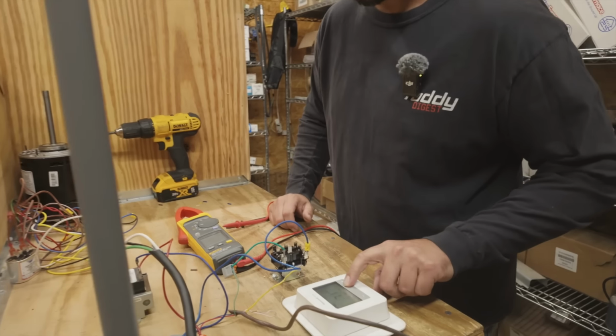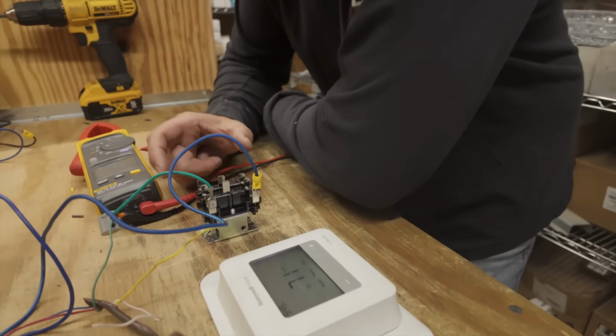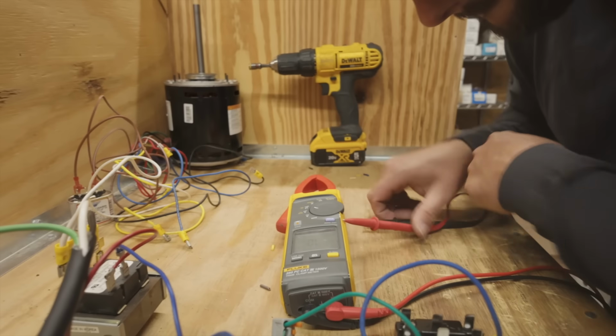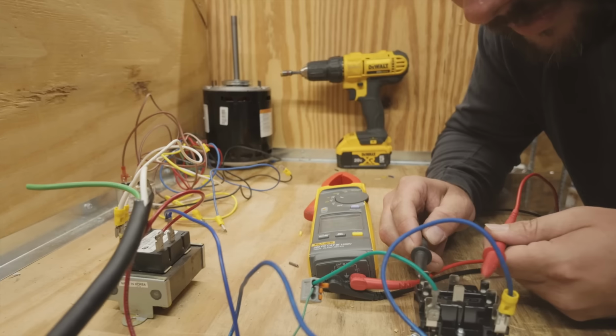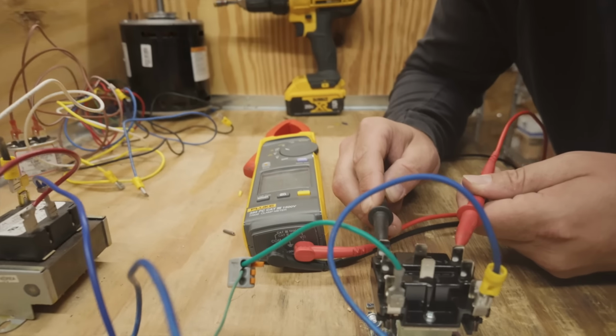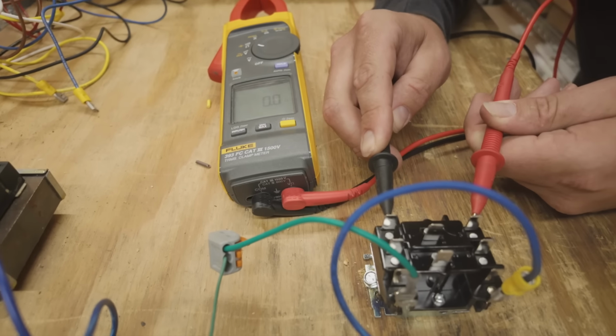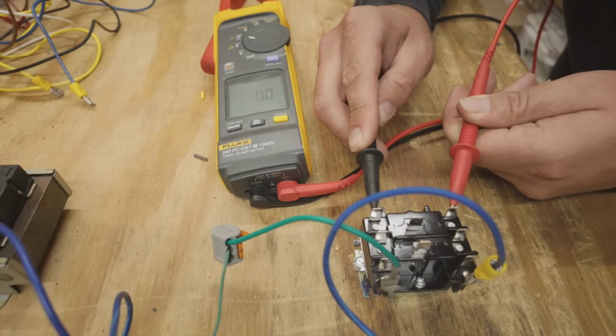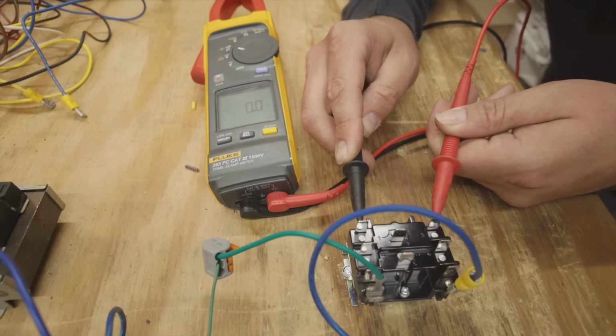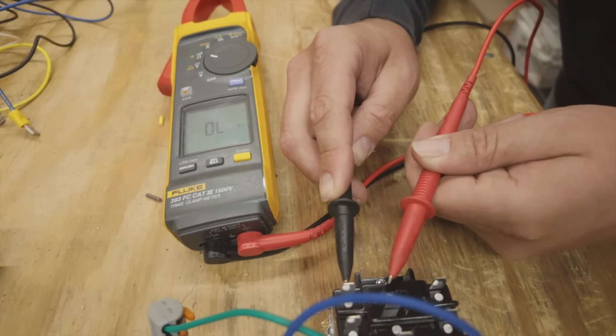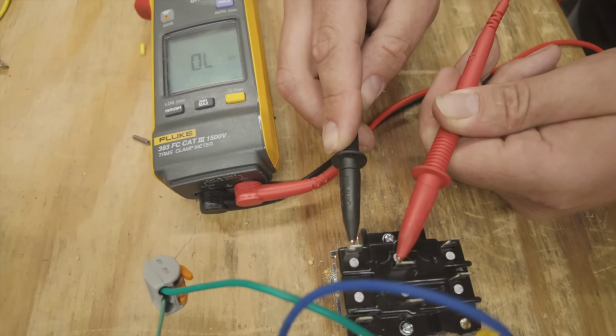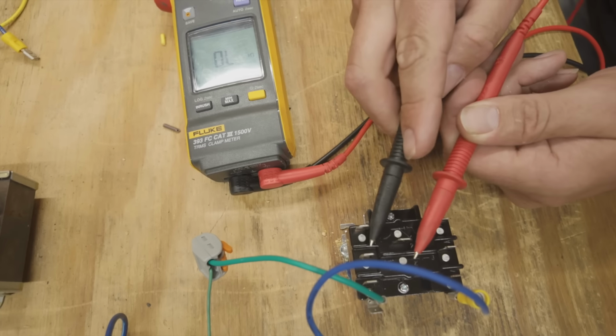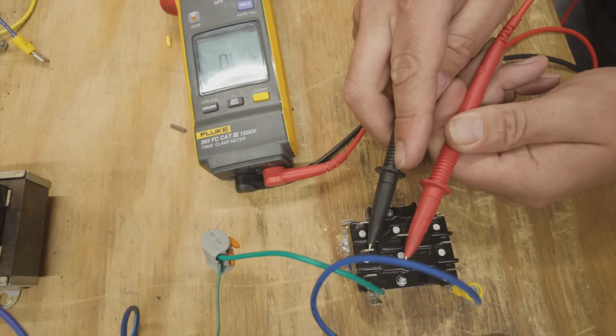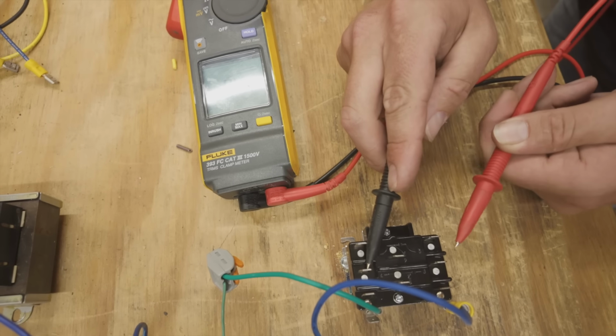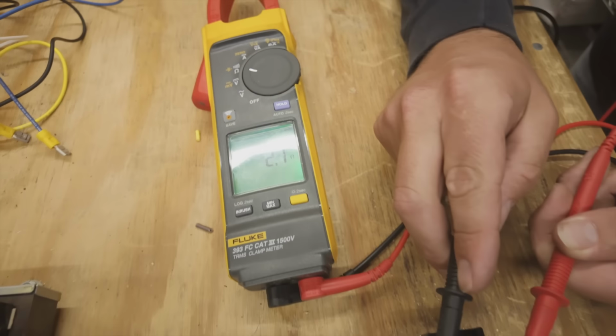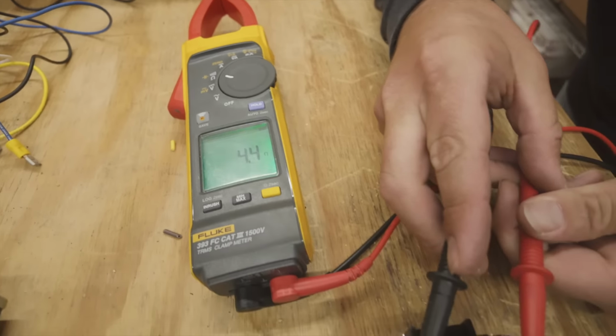Now we've got it disconnected. I'm going to go ahead and give it a call. You're going to hear it click. Okay? We're going to put our meter here. 1 to 3. See how it's not closed? Oh, what happened? It closed. So you can see we've got voltage now. But 1 to 2 was closed, but look, now it's not. 4 to 5 was closed. Now it's not. But 4 to 6 is. Look. See, it's closed.